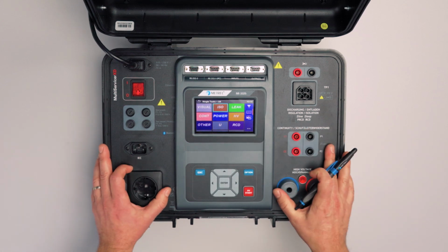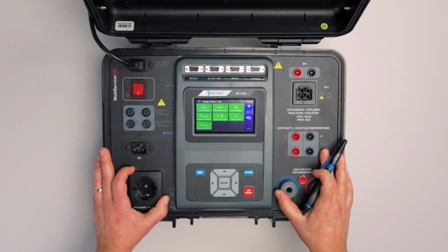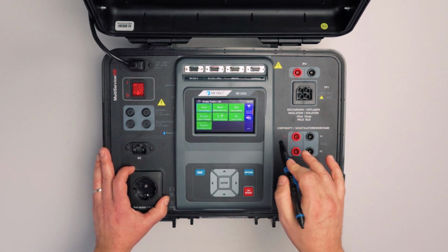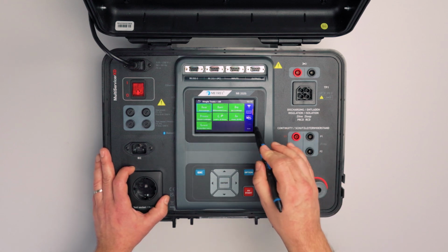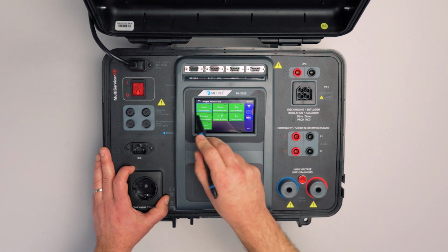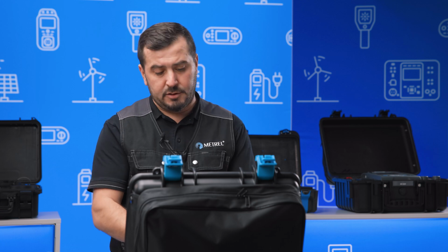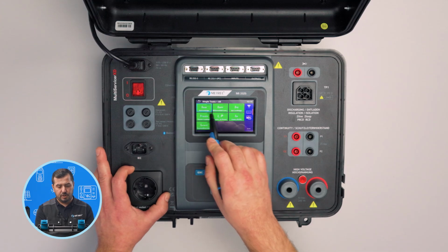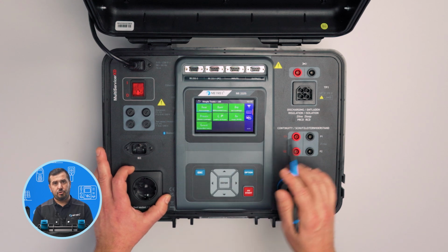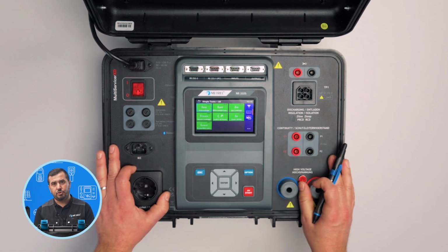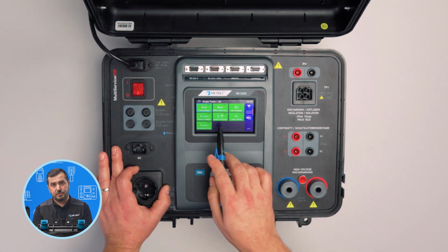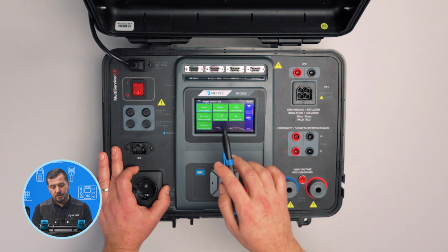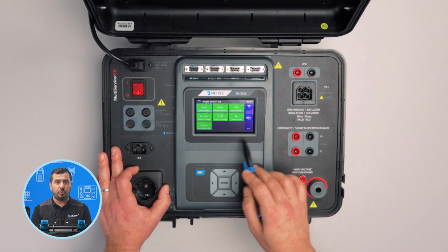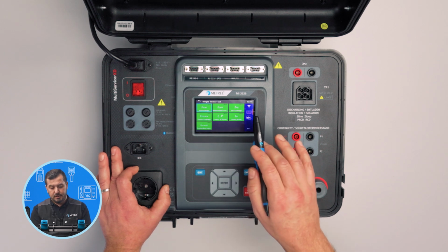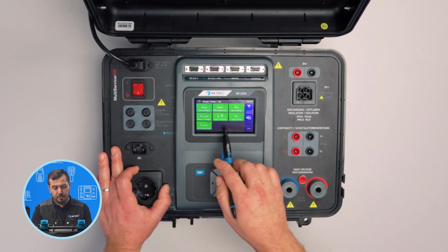The next group inside the single tests is the leakage group. Here again we can choose between different leakage current test methods. The first three are dedicated to the PE conductor leakage test with, as I said, different methods: substitute leakage or alternative method, differential leakage or residual current method, and EPA leakage or the direct method. Then, of course, we also support the touch leakage, leakage and power, and leakages for welding equipment. These are welding equipment leakage and protective conductor leakage.